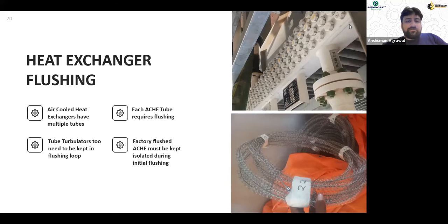Now, what people do is they check the port size of the heaters, which are normally 4 inch. They design the flushing flow rate based on the port sizes of the heat exchangers. But actually, a heater is a parallel bundle of multiple loops. And you forget to calculate the flushing flow rate through the multiple loops of the heat exchanger. So we have actually checked that when you have to flush a heat exchanger or ACHE, which is an air-cooled heat exchanger, which has multiple loops, you need to go to a flow rate level of around 4,000 liters per minute. Minimum is 3,000 liters per minute. So unless you do that, you're not sure about the heat exchanger flushing.